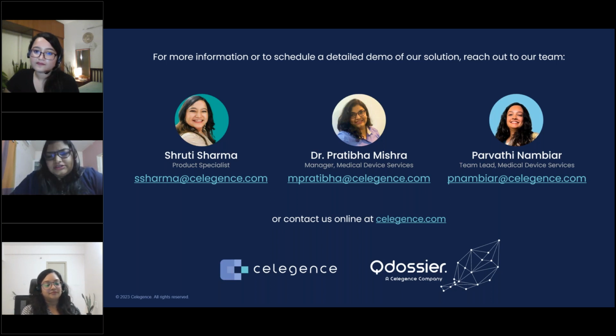Like for a radiology device, there are international standards and guidelines that your device has to comply to. The other source, like Parvati said, is clinical data from similar devices, preferably CE mark devices. You can also look at similar technologies, or even alternative therapies that are available for the same indications, and what kind of performance and safety outcomes they are having in the real world, which can come from literature.